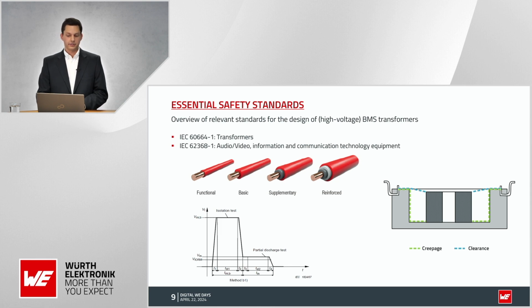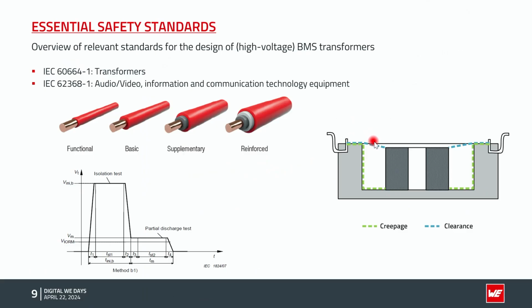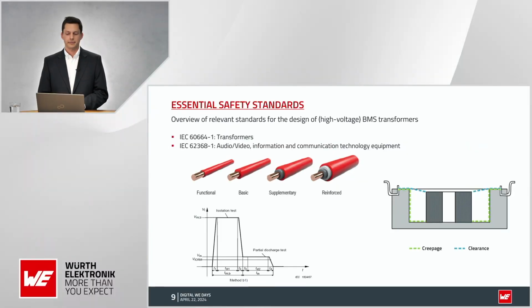The clearance distance is the shortest distance between two conductors through the air. So as you can see, the clearance is here the marked one, and the creepage is the other one. So it's important to ensure sufficient clearance distances in order to protect people and systems from the effects of electrical operating voltages. The required clearance is determined by determining the overvoltage category, the degree of contamination, and the operating voltage. So the minimum clearance distance can then be determined using table 14 of the above mentioned standard.